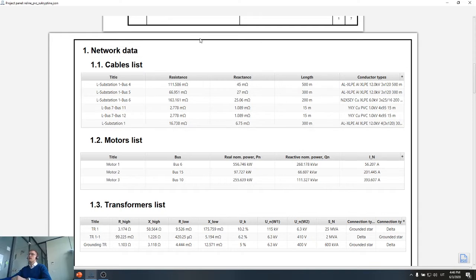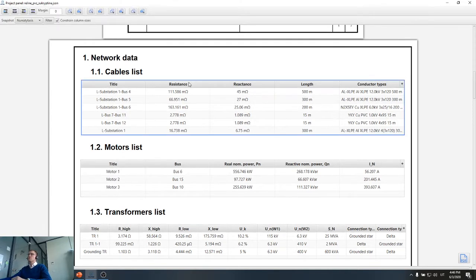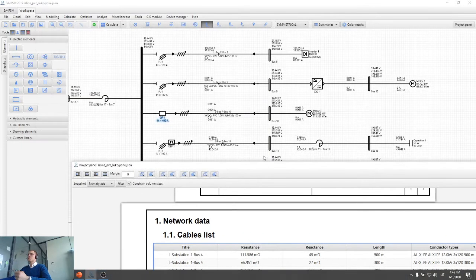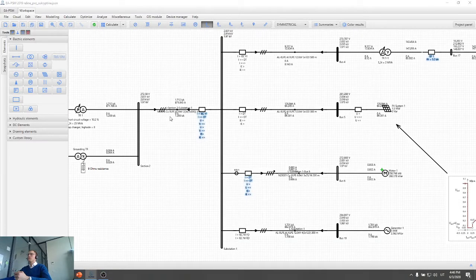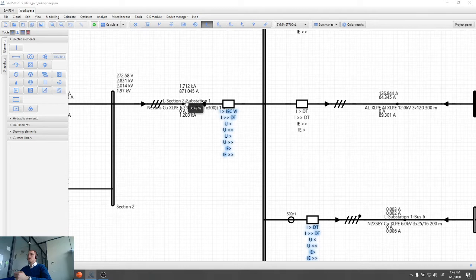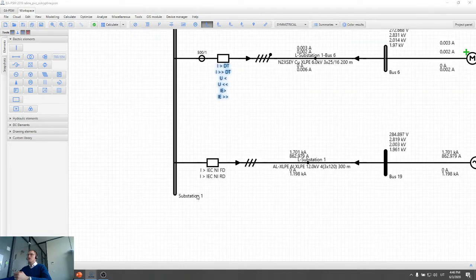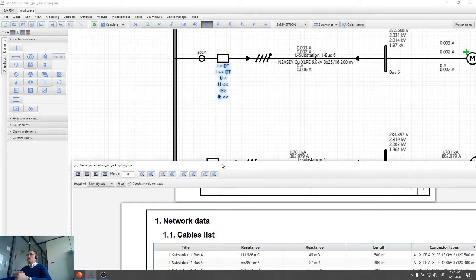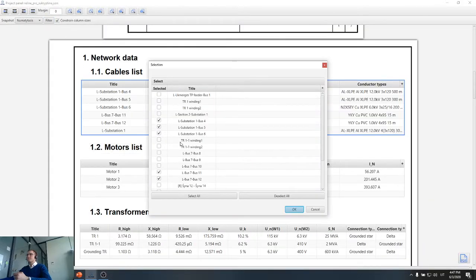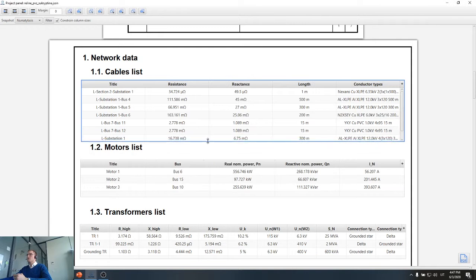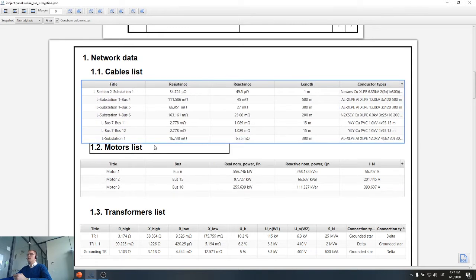The good thing about this feature is that if you make any changes to the network, you don't have to change the whole report. You can automatically change only the single table. So you remember that, for example, I added a cable here between section 2 and substation 1. So now I can add this cable. So let's see, section 2, substation 1, it's here. Yeah, so my table just automatically expands with one more cable which I have specified.